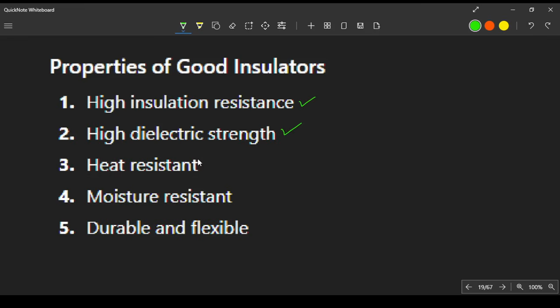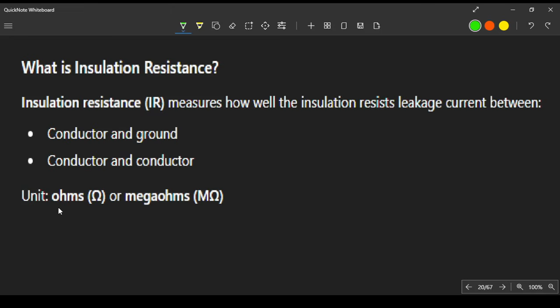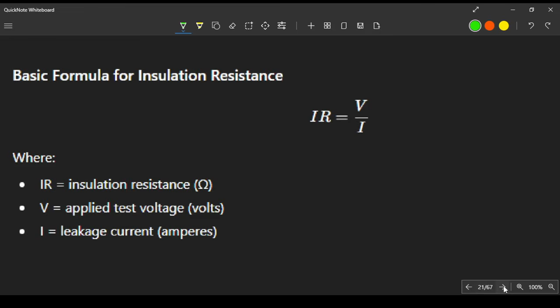Okay, then we have insulation resistance. Insulation resistance measures how well the insulation resists leakage current between conductor and ground, and between conductor and conductor. This is measured using a meter. The unit for insulation resistance is ohms or mega ohms. The formula for insulation resistance is IR equals V over I, where IR is the insulation resistance in ohms, V is the applied test voltage of the meter, and I is the leakage current in amperes.